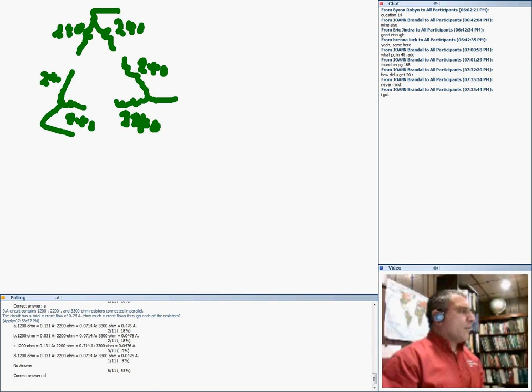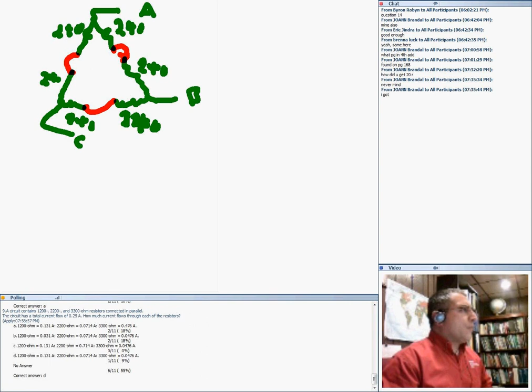So here's the motor, here's phase A, here's B, here's C coming to me. Now if I want to connect this motor to high voltage, all we have to do is tie these two ends together with a wire nut. Now this motor is running high voltage - add the 2 voltages together to get 480. You get yourself a delta 480 motor. Look at the coils - the coils are connected in series now.